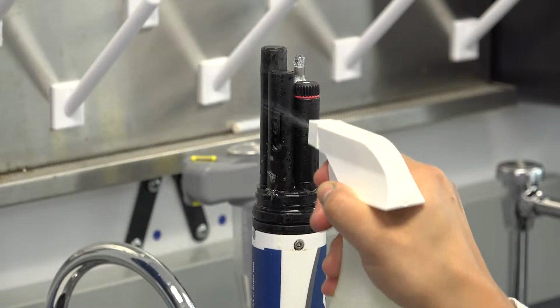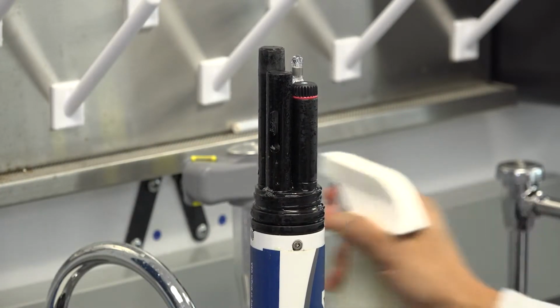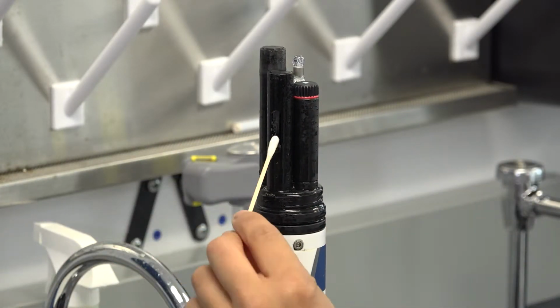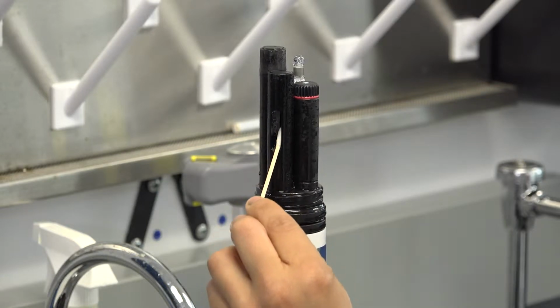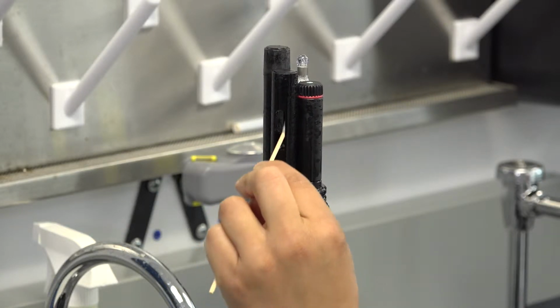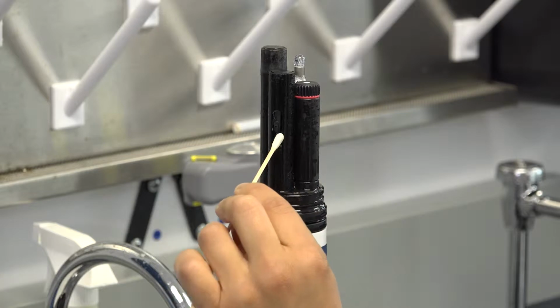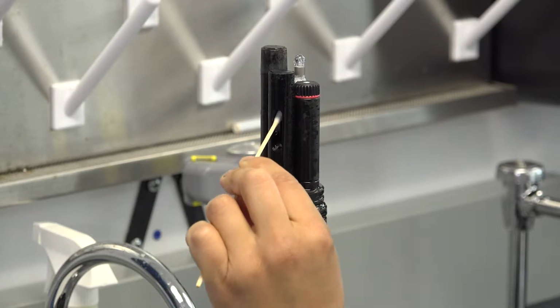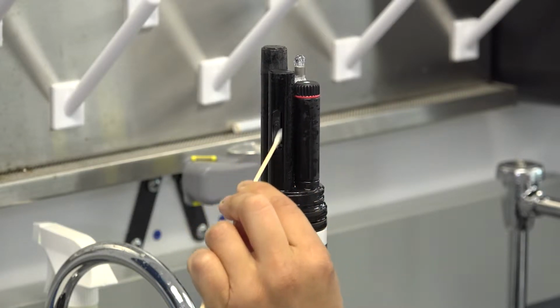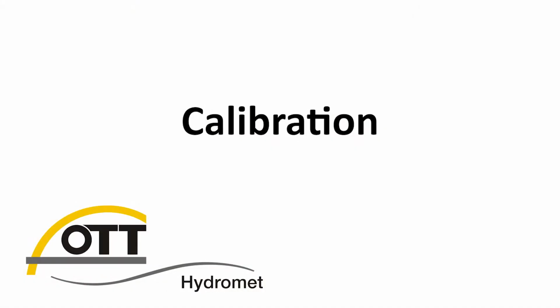The inside of the cell should be cleaned out after every deployment with a cotton swab or small brush. Additionally, prior to calibration of conductivity, all sensors should be cleaned. Any residue or debris on the sensors may contaminate the conductivity standards and change their value, resulting in an inaccurate calibration.